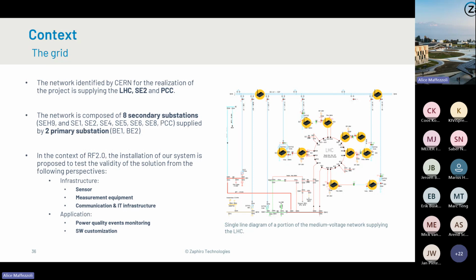In standard grids, with our SynchroSense, we rely on voltage and current measurement in the primary substation and only current measurement in the secondary substation. But for this project, as there were already available current and voltage measurement, and for the peculiarity and aim of the project - power quality monitoring - in this case we are monitoring current and voltages everywhere.